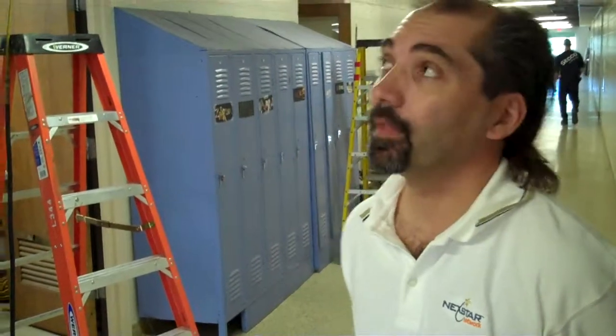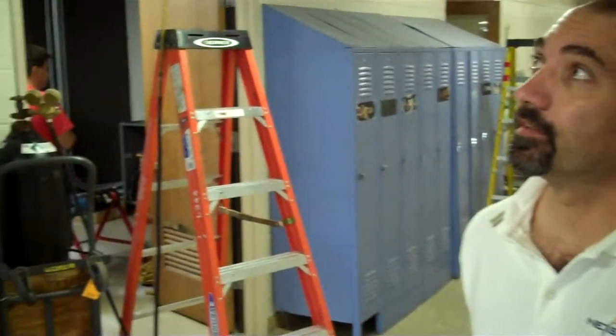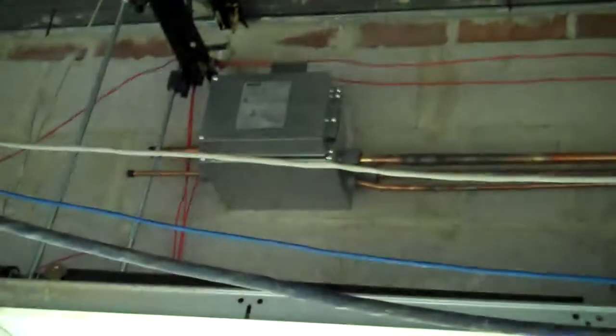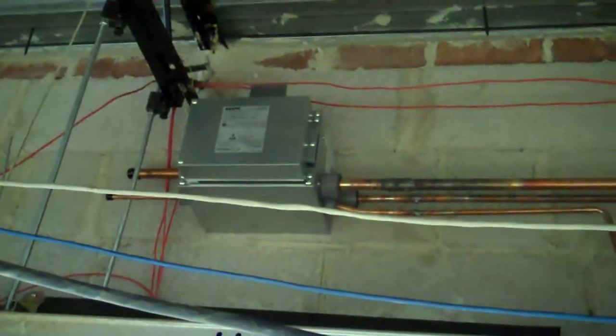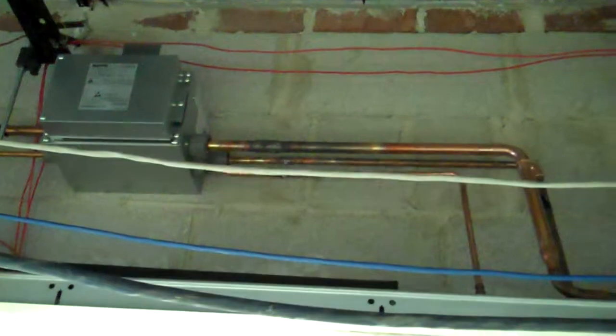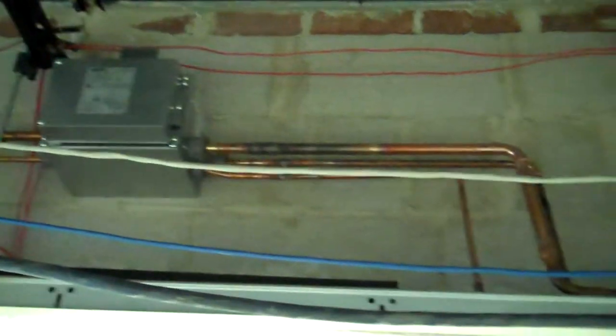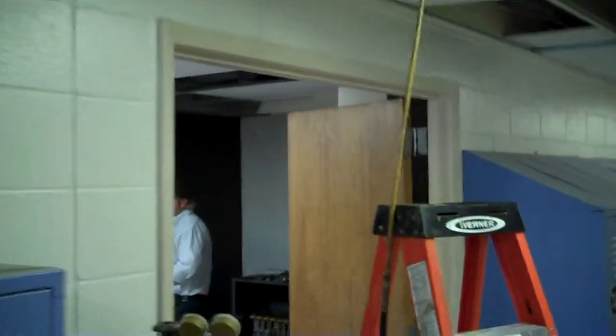Fishing Creek Elementary School in Harrisburg, PA, and we're installing an Eco Ductless system, a high efficiency heat pump system that does simultaneous heating and cooling. And right now we're just looking at the rough-in on some of the solenoid boxes that control the air handlers. What's really neat about these solenoid boxes is we'll be able to pump the system down if we should have a problem with any one of the air handlers, so we wouldn't have to recover 30-40 pounds of refrigerant for the entire system. And it's great for the technicians to be able to come in, get out, get repairs done.